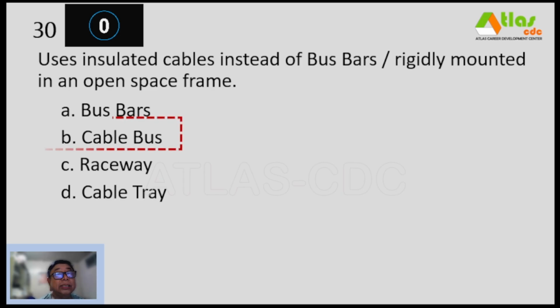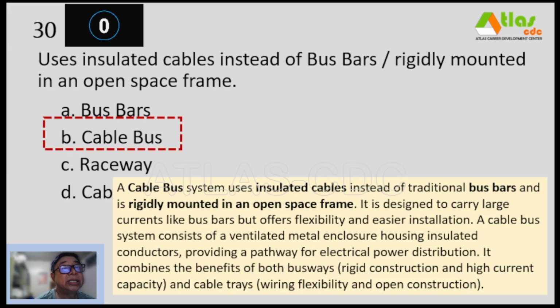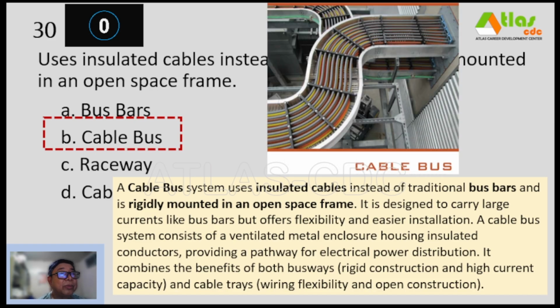And our correct answer is letter B, cable bus. So a cable bus system uses insulated cables instead of traditional bus bars and is rigidly mounted in an open space frame. It is designed to carry large currents like bus bars, but offers flexibility and easier installation. A cable bus system consists of a ventilated metal enclosure housing insulated conductors, providing a pathway for electrical power distribution. It combines the benefits of both busways, rigid construction and high current capacity, and also cable trays in terms of wiring flexibility and open construction. So ito yung cable bus, no?